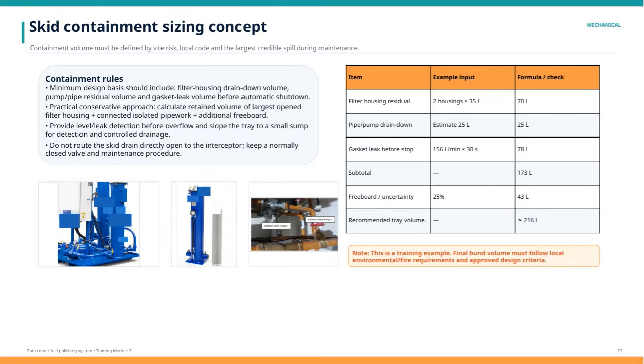Here we are looking at the skid containment sizing concept, which is crucial for ensuring safety during maintenance activities. The containment volume must be defined by considering the site-specific risks, local regulations, and the largest credible spill that could happen while performing maintenance. Mechanically speaking, the containment rules emphasize a minimum design basis that accounts for several factors: the drain-down volume from the filter housing, any residual volume in pumps and pipes, and potential leaks from gaskets before an automatic shutdown occurs. A practical and conservative approach is to calculate the retained volume of the largest open filter housing alongside any connected isolated piping, plus an additional freeboard to account for uncertainties.